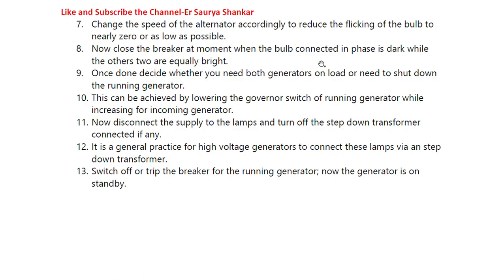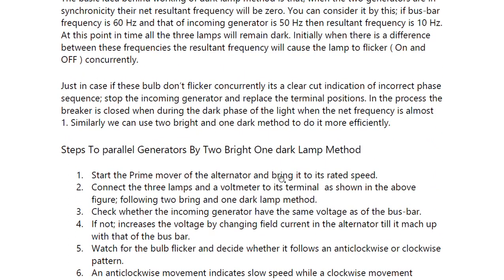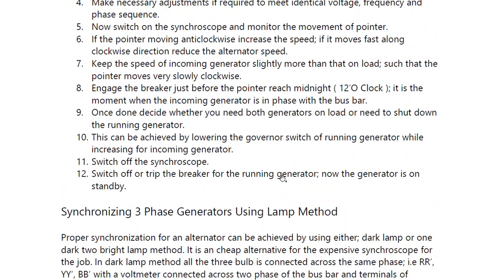Close the breaker at the moment when the bulb connected in phase is dark while the other two are equally bright. Once done, decide whether you need both generators on load or need to shut down the running generator — lower the governor switch of the running generator while increasing it for the incoming generator. Disconnect the supply of the lamps and turn off the step-down transformer if any, as it is common practice for high-voltage generators to connect lamps via a step-down transformer. Switch off or trip the breaker for the running generator; it is now on standby.